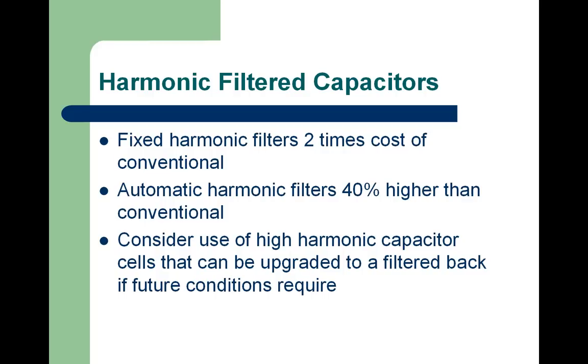Converting a 100 kVAR capacitor bank to being filtered would probably cost slightly more than adding a tuning reactor to a motor that only required 25 kVAR. Being that a 25 kVAR tuning reactor is certainly not, it would be a half to 50% of a 100 kVAR tuning reactor. So once we get into distributed capacitance throughout a facility, as long as we are not going to have any harmonic issues down the road, it's probably the best way to go. The I squared R loss recovery makes a lot of sense. But these days, with more and more variable frequency drives, new DC drives, etc., the requirement for filtered banks is becoming greater and greater.